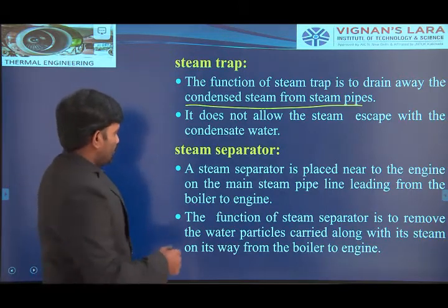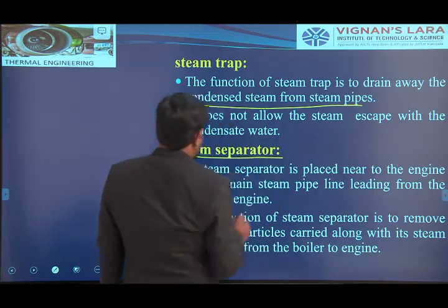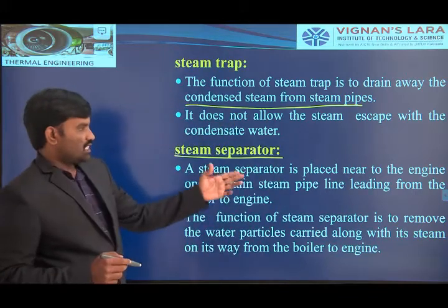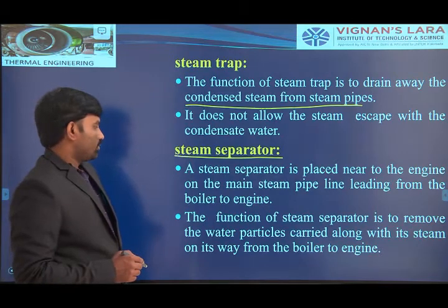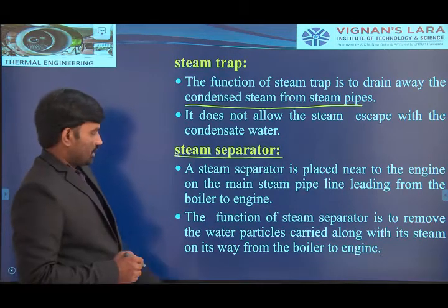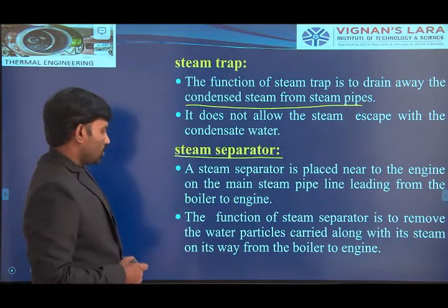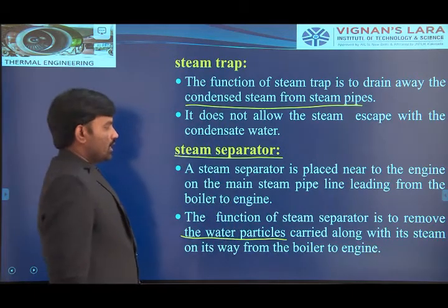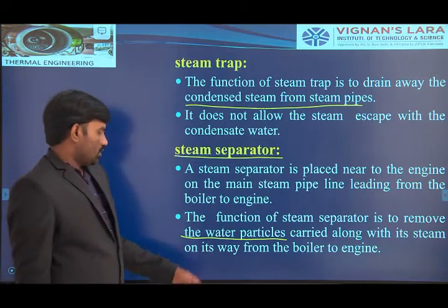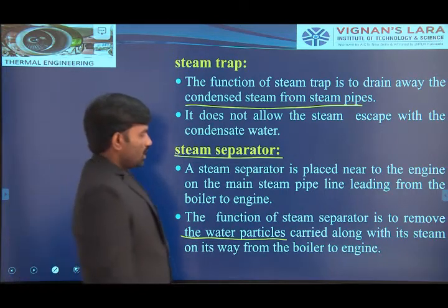And the steam separator. A steam separator is placed nearer to the engine on the main steam pipeline leading from the boiler to the engine. The function of the steam separator is to remove the water particles carried along with the steam on its way from the boiler to the engine.